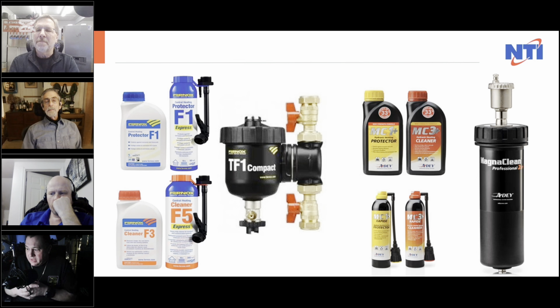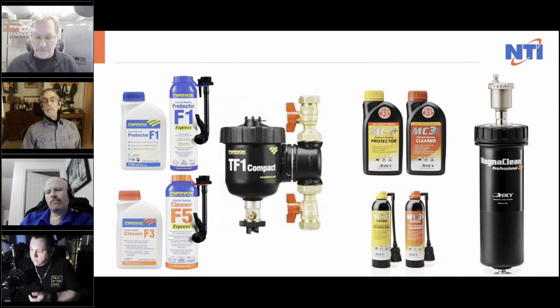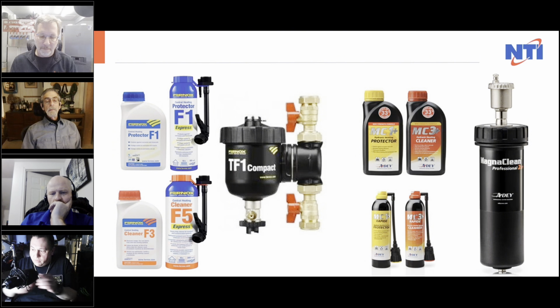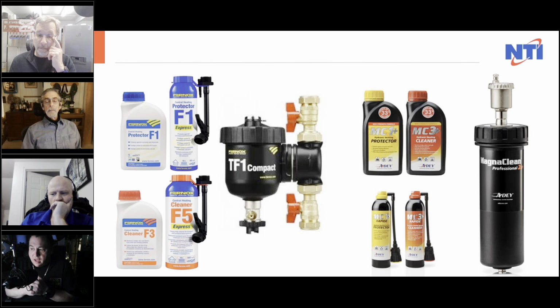The cool thing is now you don't have to jump up with a TSP. Now you guys can just walk up to a boiler drain. I always tell contractors, when your estimator gets a signed contract and signed proposal saying they want that NTI boiler put in, that's when the estimator should be trained to go down to the boiler drain, hook this up. It's self-injecting. Open up the boiler drain, let it run through the system for 2 weeks. Then when the guys come to install the boiler, all they have to do is drain it down, run a little fresh water through it, and get all that magnetite out. It's not hard, it's not like they have to rip the boiler apart.